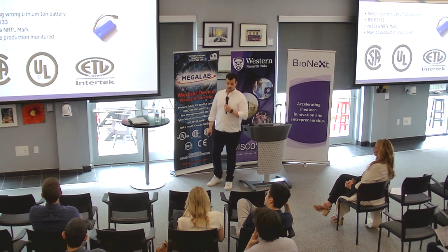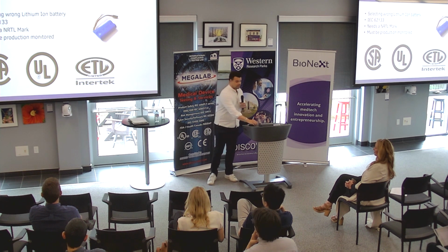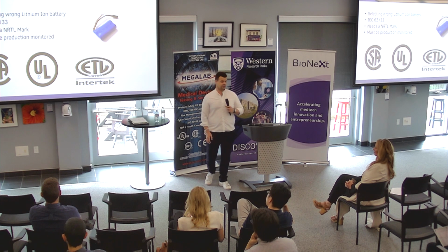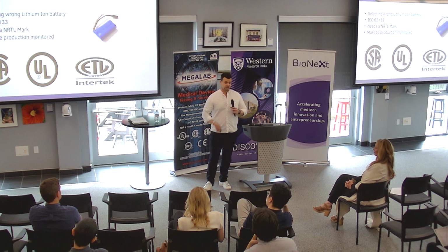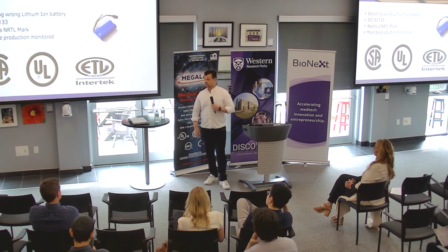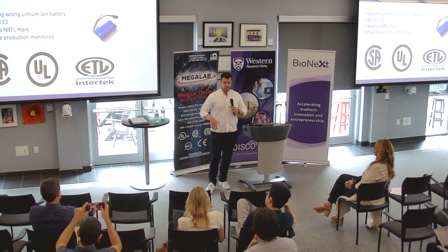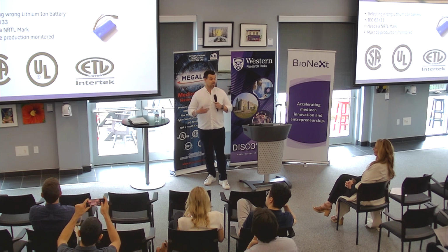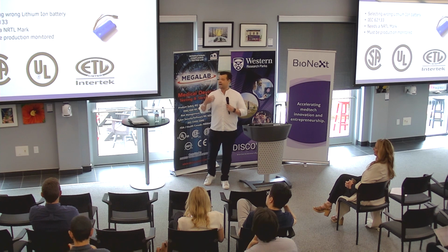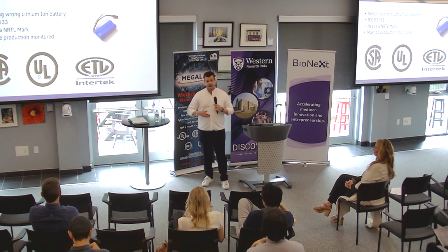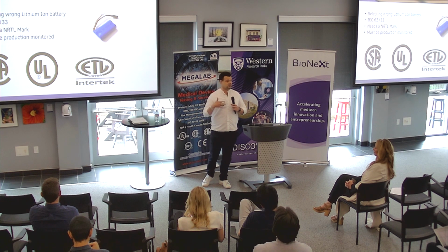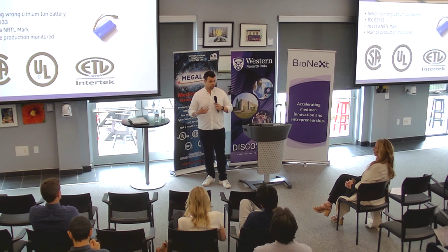This one was a big one a couple years ago. Selecting an unapproved lithium ion battery. So let's say you might have a medical device that doesn't even plug into the wall. It just has a lithium ion battery. So there's not a lot that can go wrong, like a mains powered device, but I'm sure you've heard all the stories. The batteries themselves can be dangerous. So what might happen is, if you're not in the industry, you don't know this, you'll say, okay, well, the guy I'm buying this from in Asia says that it's compliant, right? So says it's compliant and is compliant are two different things.